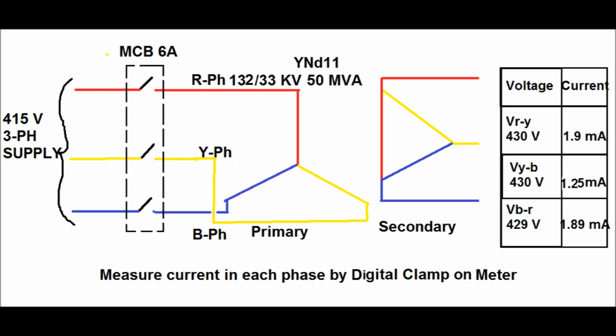The current and the voltage have been measured. Current has been measured by a clamp-on meter and recorded, and the voltage between phases has been measured by a multimeter and recorded. The recorded voltage and current are shown in the table on the right side of the diagram.